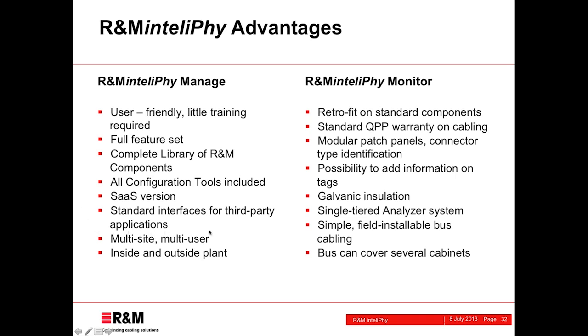We have standard interfaces for easy integration with third-party applications. The system supports multiple sites, is a multi-user system, and can document both inside plant and outside plant networks. On the hardware side, R&M inteliPhy Monitor is fully retrofitable on standard R&M components — no special panels, no special patch cords. Everything can be upgraded from non-intelligent to intelligent, and the standard R&M 25-year lifetime warranty on the cabling plant stays intact even when inteliPhy Monitor components are retrofitted. Thanks to RFID technology, we can do connector type identification and support modular patch panels mixing different technologies and connector types in the same unit.